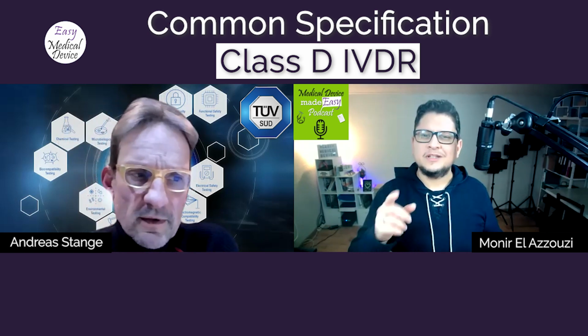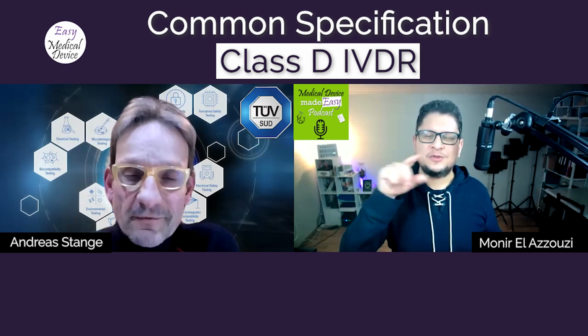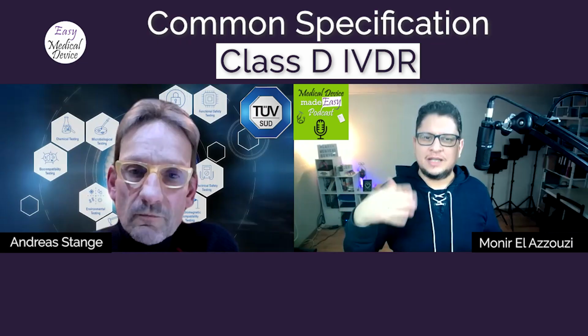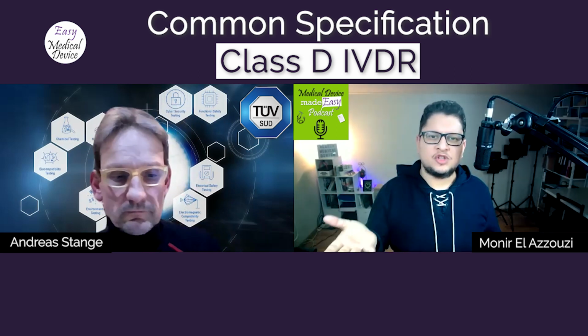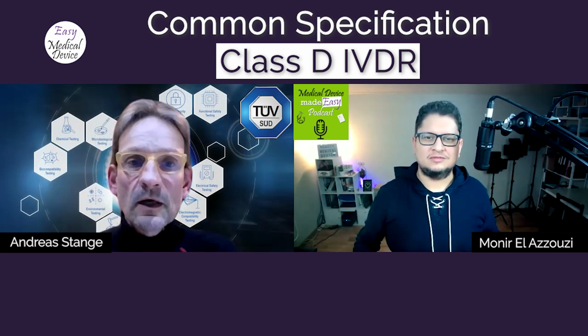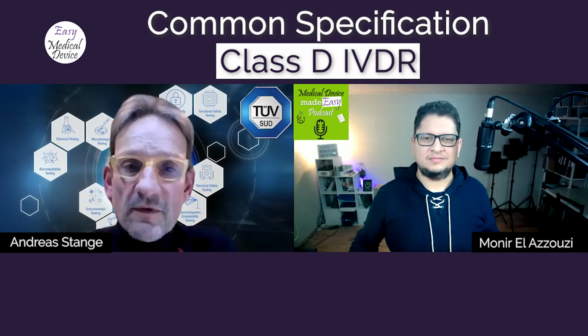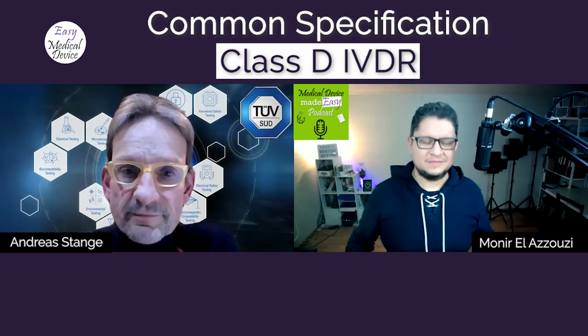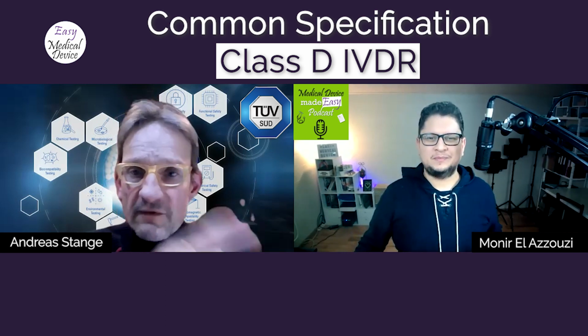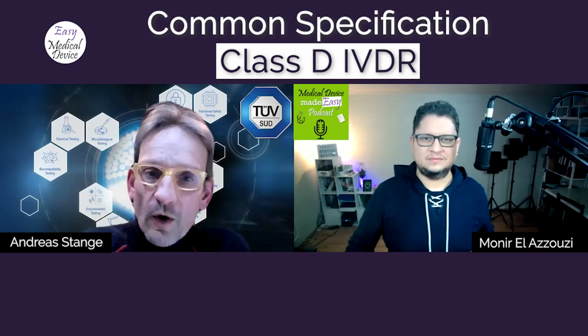Okay. So just to come back to what you said before, for the second batch, can we certify them without those common specifications? Yes, we can. But we then need to go through the expert panels. Okay. So the way through the expert panel is now open, and regardless of whether we have common specifications or not, Class D devices can be certified. But the way is a little bit longer.